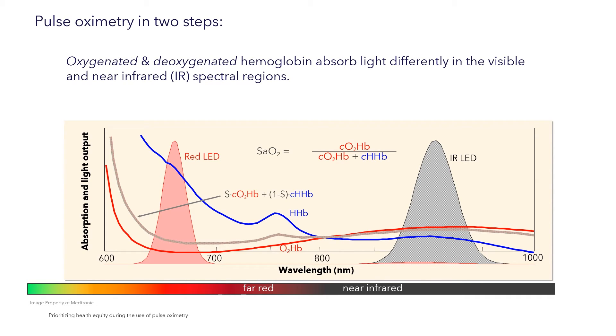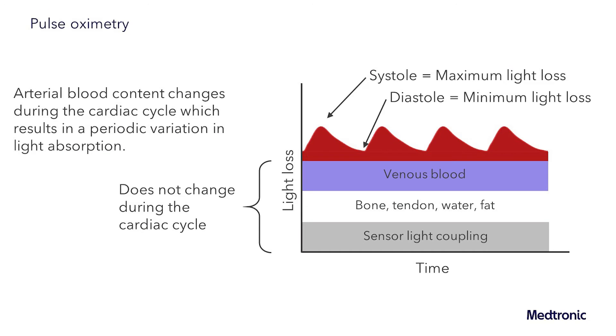Pulse oximetry measures the pulse or plethysmography wave as arterial blood content changes during the cardiac cycle, resulting in periodic variations in light absorption. During systole, as the vessel expands, maximum light loss or absorption occurs, whereas during diastole, as the vessel contracts, minimum light loss or absorption occurs.